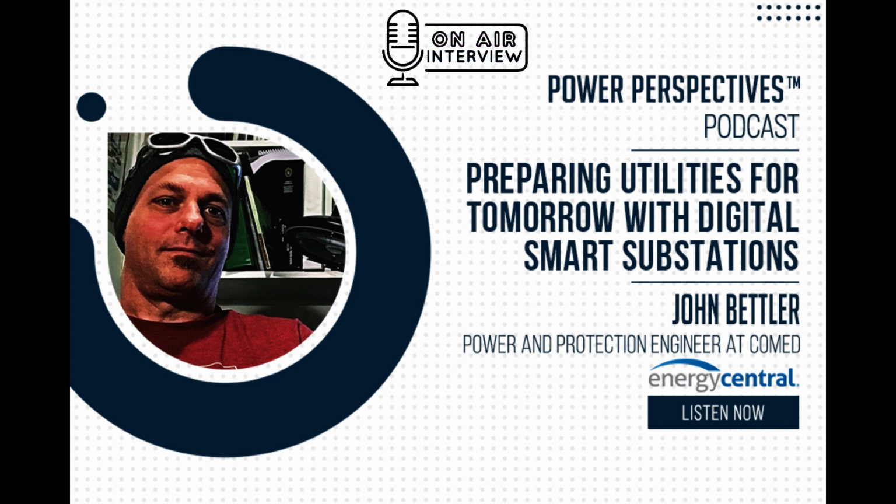Another aspect would be to have good monitoring systems in there. Are you actively monitoring your transformers or your circuit breakers? And when I say circuit breakers, are you looking at your open times, your close times? On a transformer, are you taking a look at your oil and doing online monitoring? And when I say online monitoring, it's almost like getting a Fitbit for your transformer. Do you have that in place? And I would say at a digital smart substation, that would be a requirement.